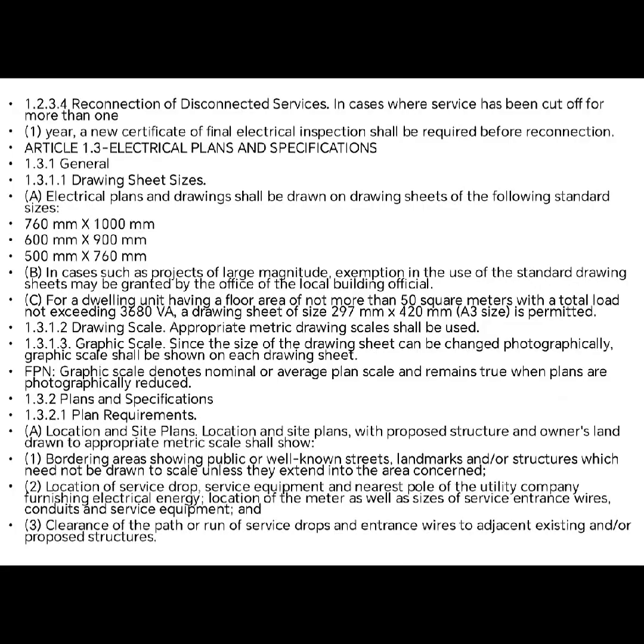Article 1.3 Electrical Plans and Specifications. 1.3.1 General. 1.3.1.1 Drawing sheet size. Electrical plans and drawings shall be drawn on drawing sheets of the following standard sizes: 760 mm times 1000 mm, 600 mm times 900 mm, 500 mm times 760 mm. In cases such as projects of large magnitude, exemptions in the use of the standard drawing sheets may be granted by the office of the local building official. For a dwelling unit having a floor area of not more than 50 square meters with a total load not exceeding 3,680 VA, a drawing sheet of size 297 mm times 420 mm, A3 size, is permitted.